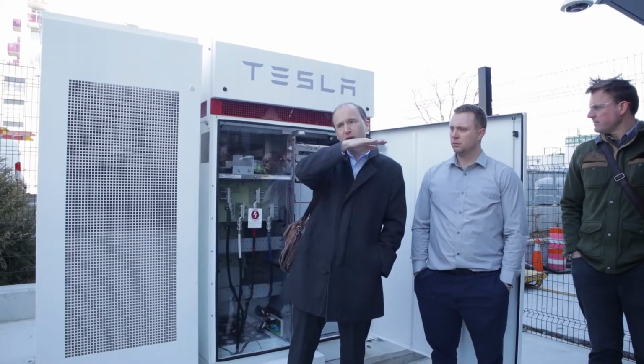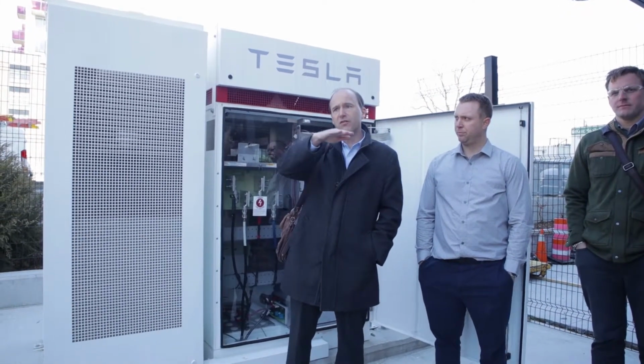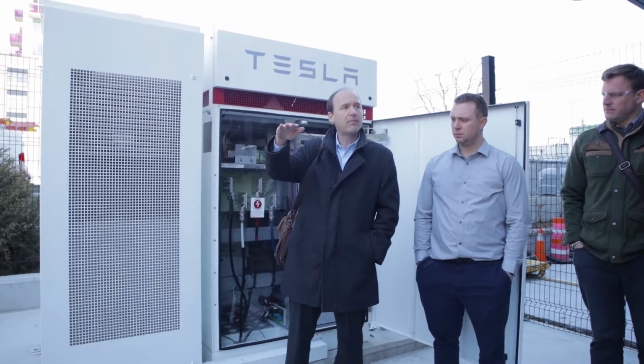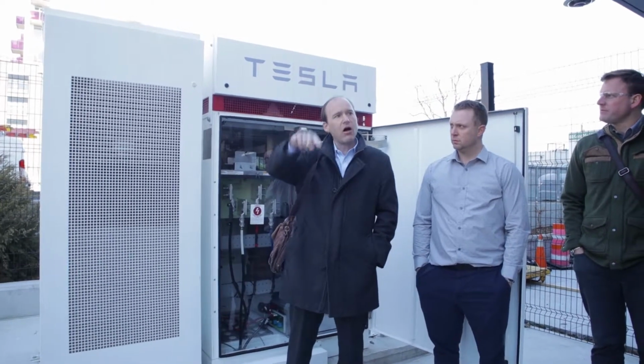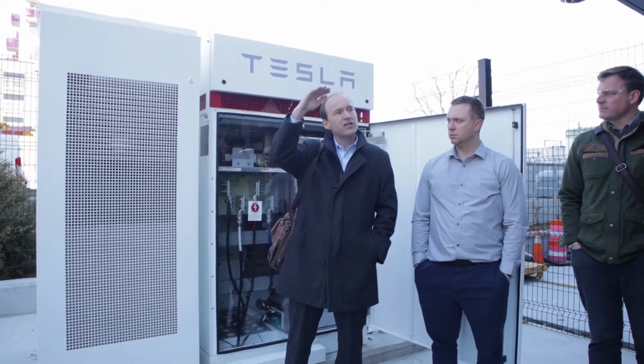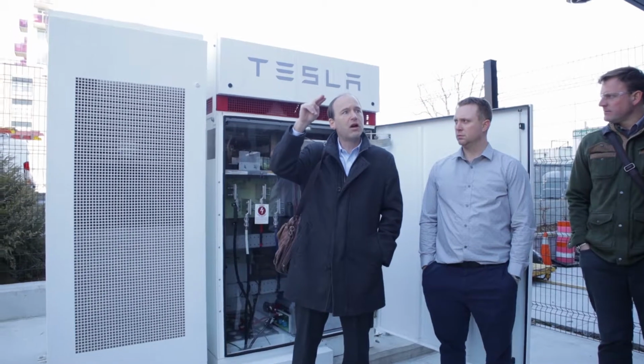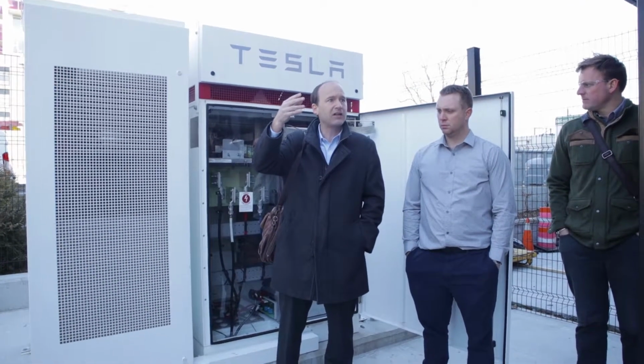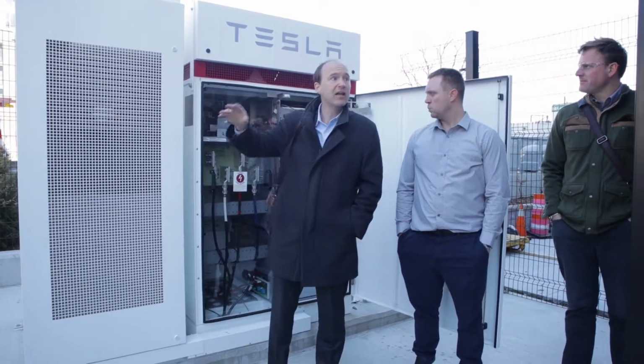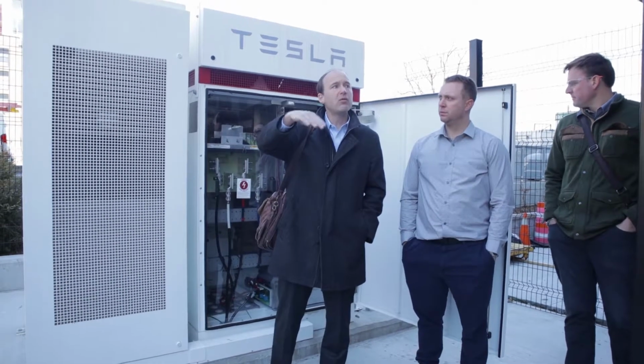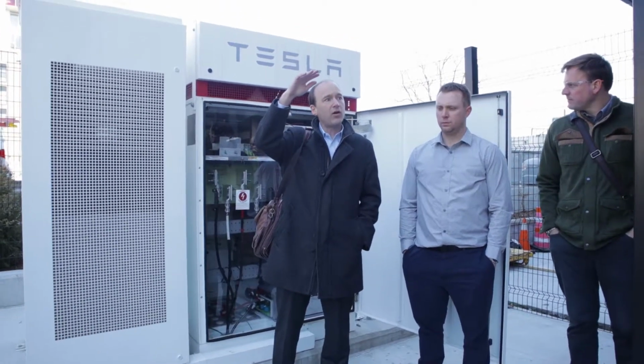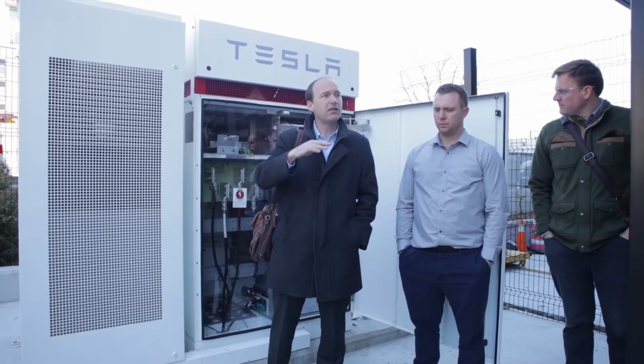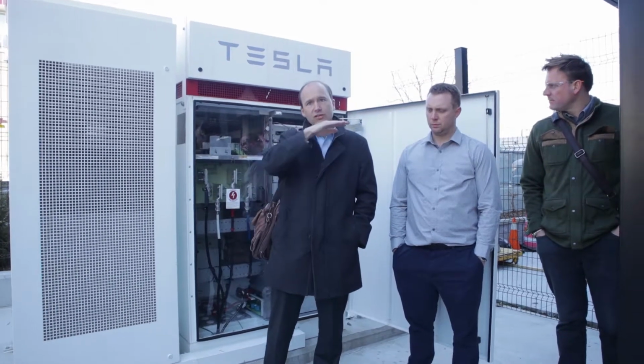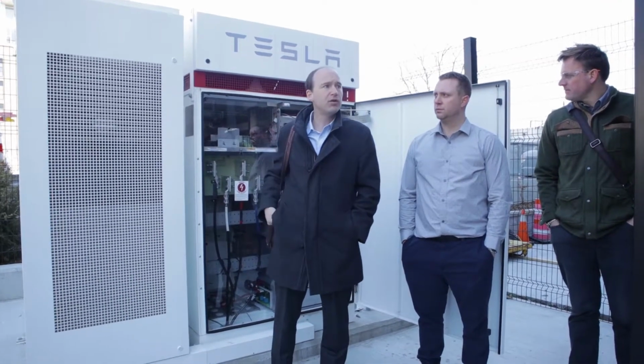So if one customer has an average consumption of 300 kilowatts, but another goes up and down all the time rather than smooth, we're going to charge that person who goes up and down more, because we're going to have to build more capacity. So they can use this battery to smooth out their load—when their demand is high, they turn the battery on, and when it's low, they turn the battery off and charge it. This way it can smooth their profile and reduce demand charges.